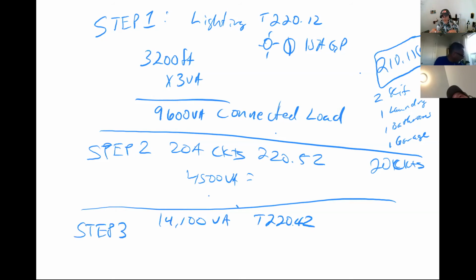You have a 2017 edition, right? That's what you got there? Yeah, okay, 2017. All right, so at the very top of that table it says dwelling units. There's 3 rows. So of this total connected load, which is the combined step 1 and step 2, I'm going to not ever be able to derate or touch the first block of 3,000 of that number.